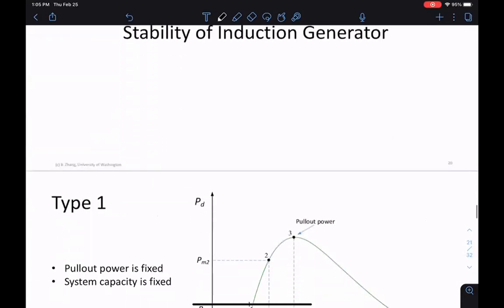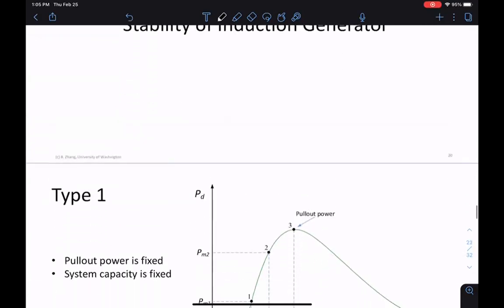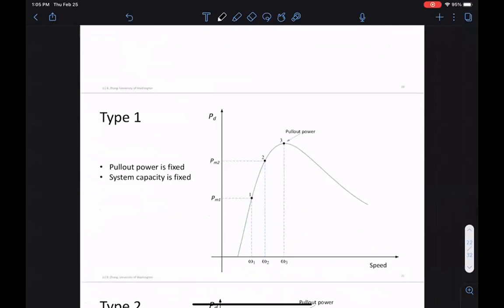So you can look at stability of induction generators, and it's pretty much the same thing. There is a max power, pull-out power, and you should operate on the left-hand side of this. You always operate on the left-hand side, not on the right-hand side of the max power. You typically want to give yourself a little bit of buffer, a margin about how far away you can operate.